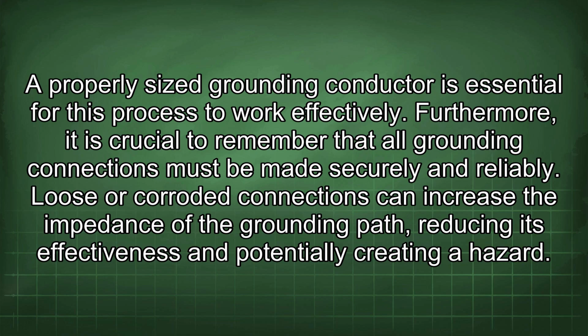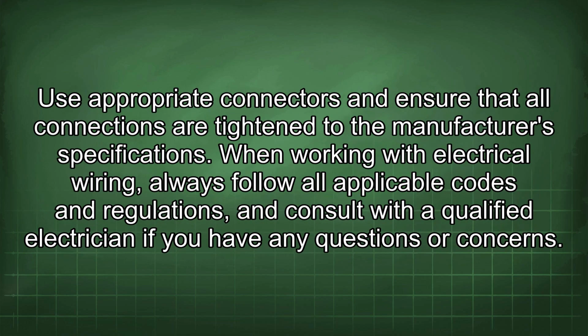Furthermore, it is crucial to remember that all grounding connections must be made securely and reliably. Loose or corroded connections can increase the impedance of the grounding path, reducing its effectiveness and potentially creating a hazard. Use appropriate connectors and ensure that all connections are tightened to the manufacturer's specifications. When working with electrical wiring, always follow all applicable codes and regulations, and consult with a qualified electrician if you have any questions or concerns.